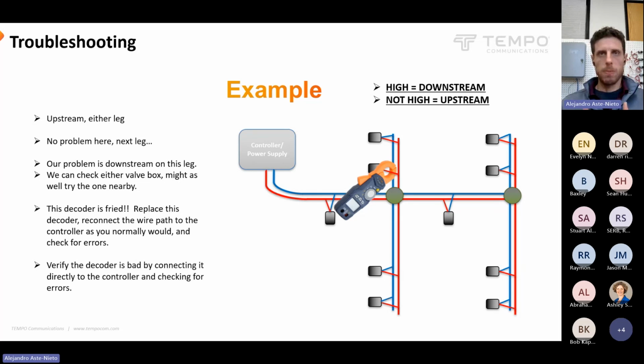So that ignores frequencies. This clamp meter is always measuring alternating current, and that's electricity wiggling back and forth on these wires, and the frequency with which that happens on the plug coming out of your wall is 60 hertz. So some systems will use 60 hertz. Some of them will use very low frequencies, like I said, like 1.2 hertz and things like that. But sometimes the communication happens at higher frequencies. The low pass filter on the CMA360B means it's trying to ignore everything above 160 hertz, everything happening faster than 160 times a second. So all those little communication signals, they're very quick little bursts of data happening. The low pass filter is going to ignore those, but the main current going out into the system is going to be unaffected. The idle current of the system will be unaffected.